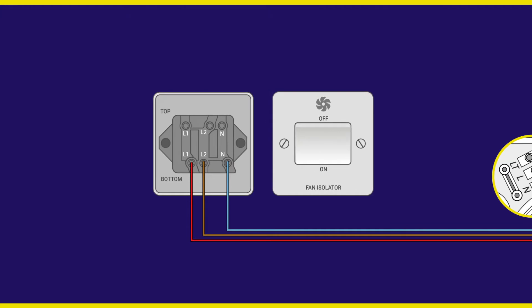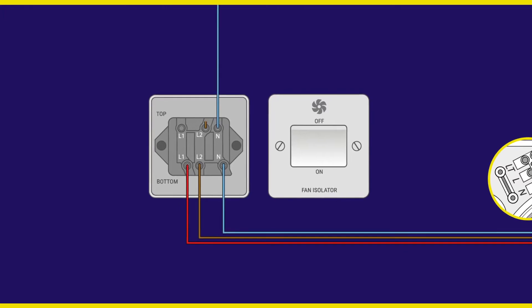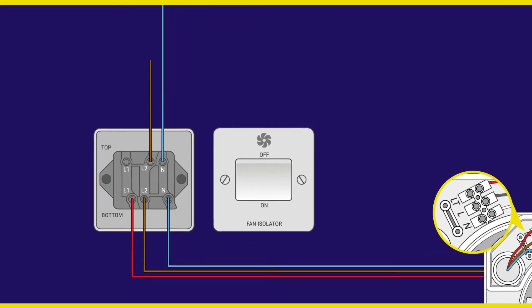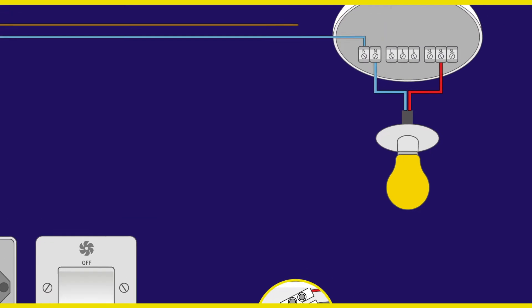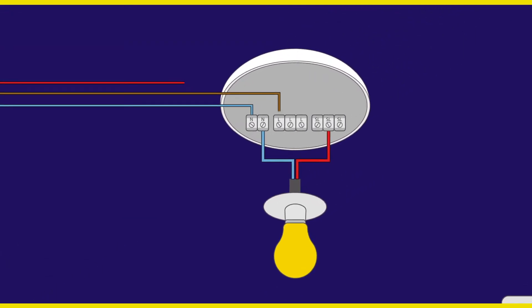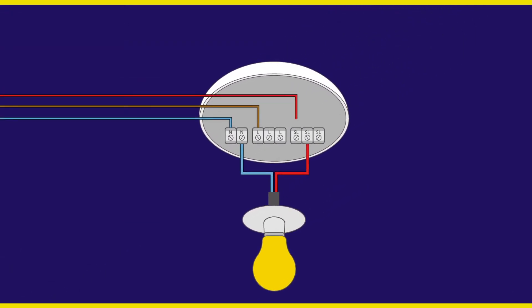Continue with your wiring from the isolator switch to your household lighting circuit. Be sure to pick up the correct connections noting that SL for switch live, L for permanent live and N for neutral are required. Again, all three connections are required for the extractor fan to function correctly.